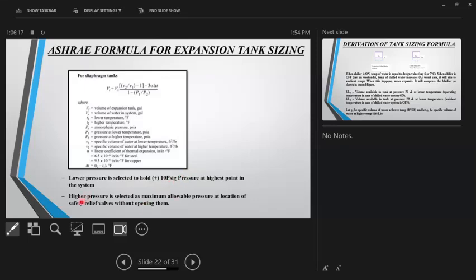And obviously the highest pressure in the expansion tank shall be such that the maximum pressure in the system should not be more than its rating, PN10, PN16 or whatever. So that's how this equation is to be used. Now, the best way to understand this equation is to see whether we can find out if it is right or wrong. In other words, if we try to mathematically derive this equation, we will understand it more.